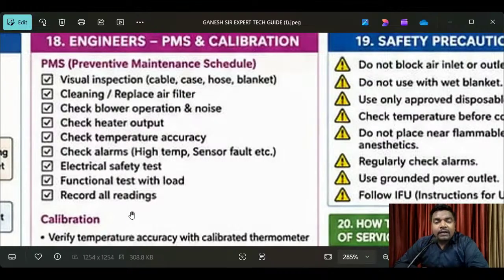Okay. So here I want to give some advice. If the equipment is not working, don't try to do the PMS, because PMS is not applicable to non-working equipment. Then what to do? You have to take the proper priority of that equipment and try to resolve it. If it is possible to resolve, then resolve it and then do the PMS on the medical equipment. If it is not in working condition, we should not do the PMS, because if equipment is not working we cannot perform preventive maintenance, right?